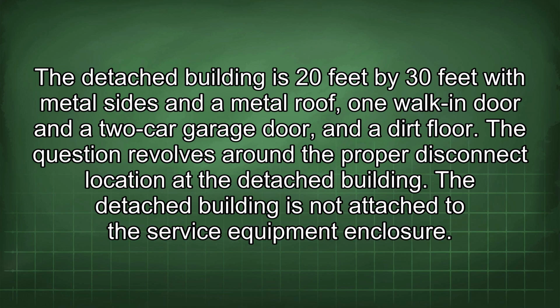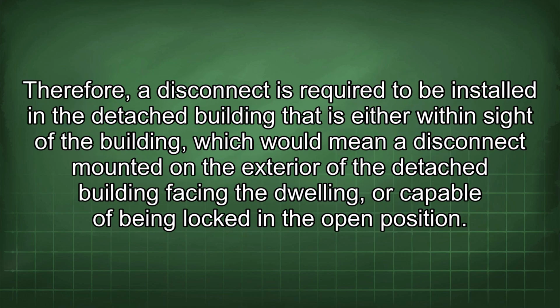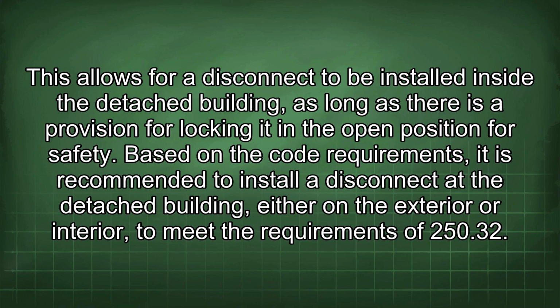The detached building is not attached to the service equipment enclosure. Therefore, a disconnect is required to be installed at the detached building that is either within sight of the building, which would mean a disconnect mounted on the exterior of the detached building facing the dwelling, or capable of being locked in the open position. This allows for a disconnect to be installed inside the detached building, as long as there is a provision for locking it in the open position for safety.